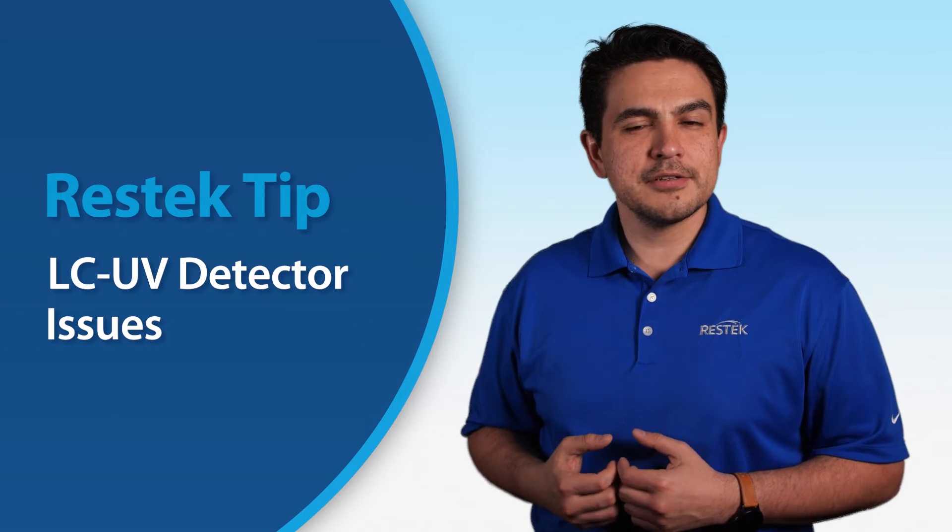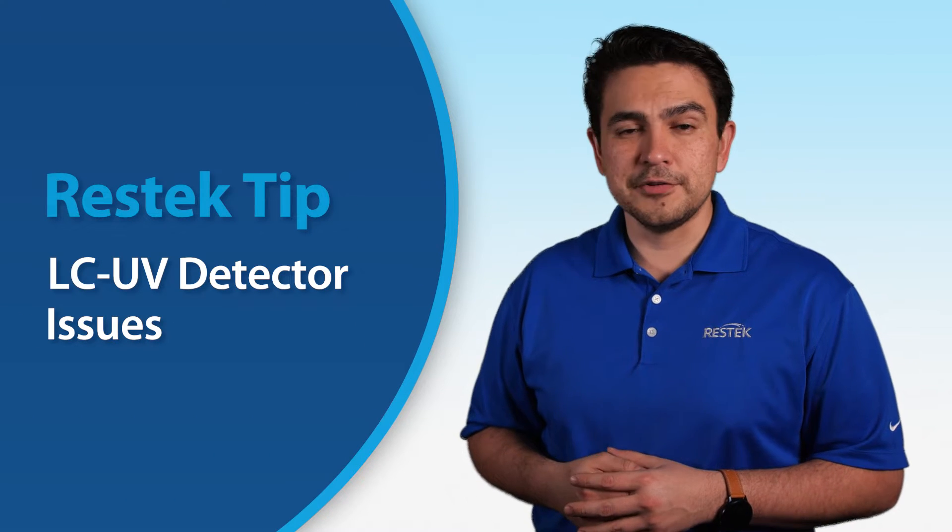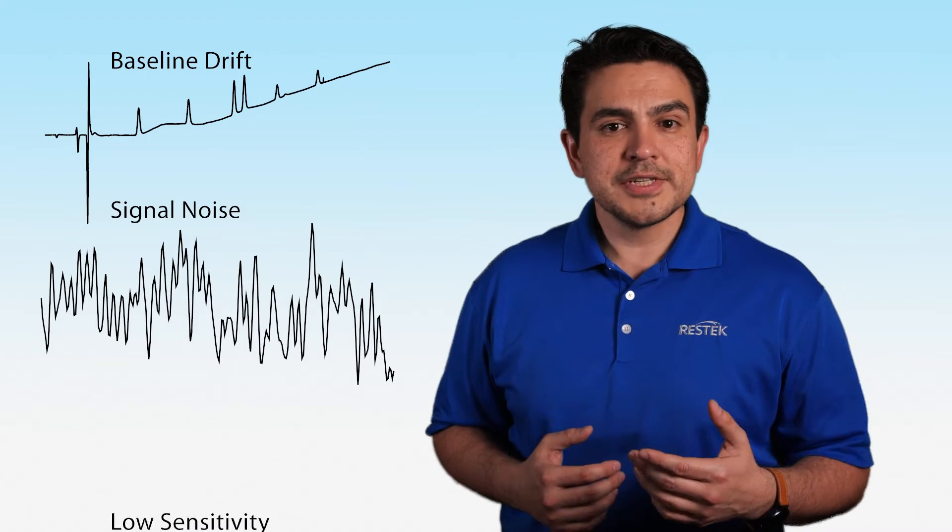In this Restek Tip, we're going to look at some of the issues you might encounter with a UV detector. What should you look out for and what troubleshooting steps can you take? Drift, signal noise, or low sensitivity in your chromatogram may be the first sign of a problem with the UV detector.